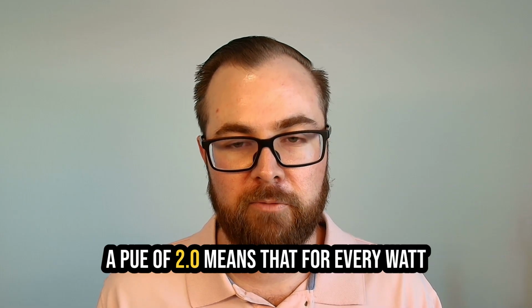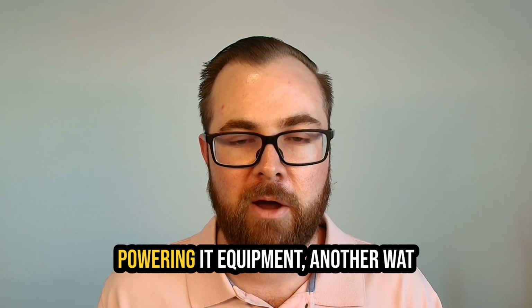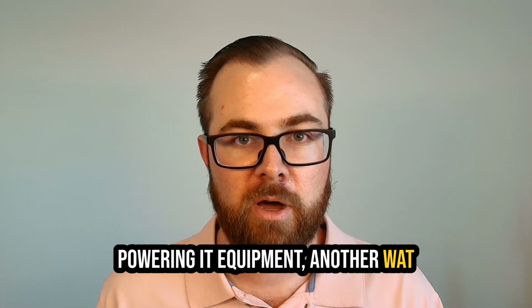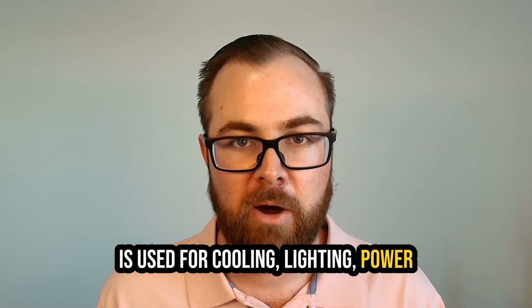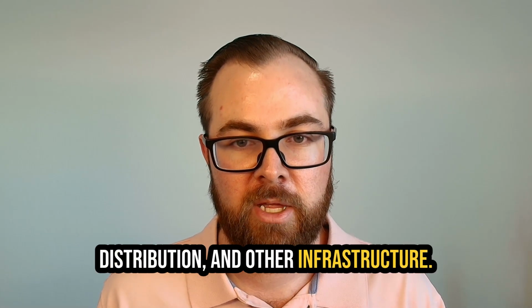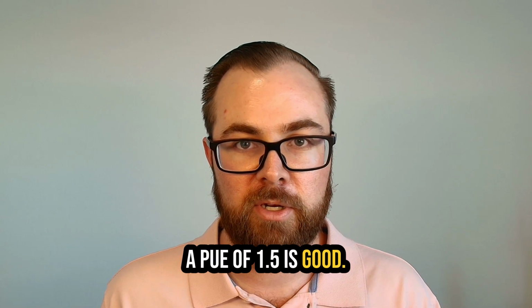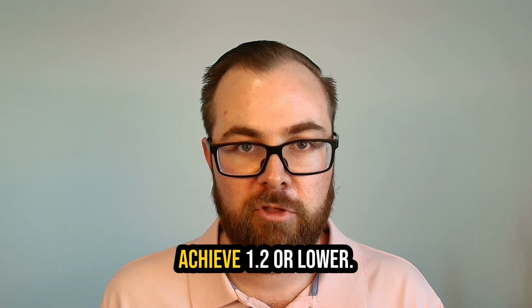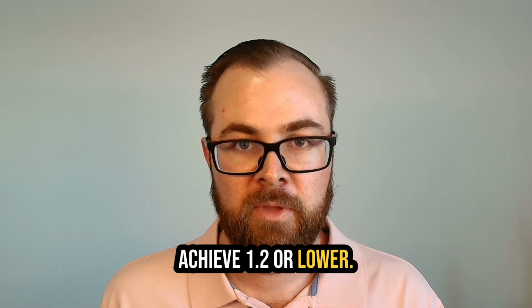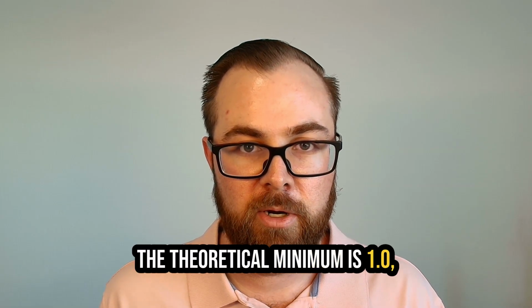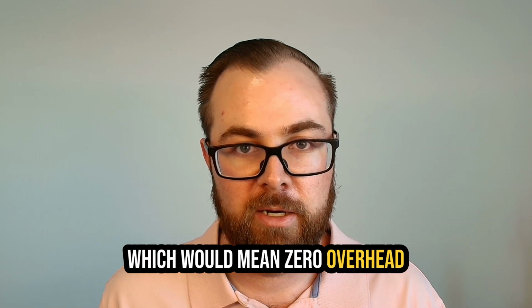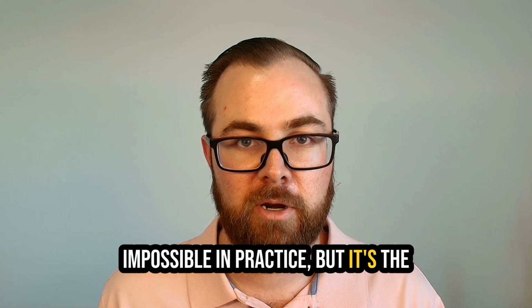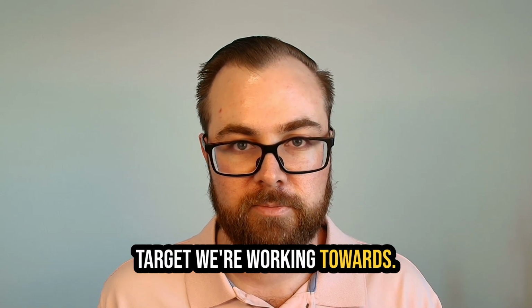A PUE of 2.0 means that for every watt powering IT equipment, another watt is used for cooling, lighting, power distribution, and other infrastructure. A PUE of 1.5 is good. Modern, efficient facilities achieve 1.2 or lower. The theoretical minimum is 1.0, which would mean zero overhead. Impossible in practice, but it's the target we're working towards.